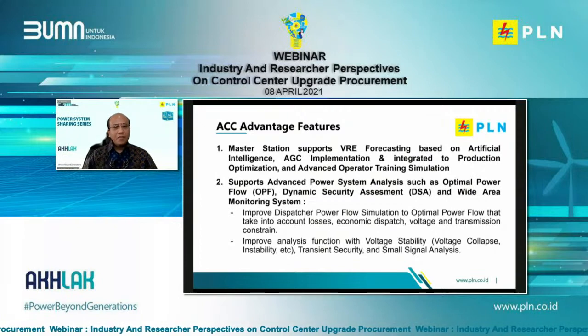Advanced power system analysis such as optimal power flow, dynamic security assessment, and wide area monitoring systems will improve the dispatcher's capability, moving from power flow simulation to optimal power flow, so we can take into account all the losses, economic dispatch, voltage, and transmission constraints, in order to achieve secure, reliable, quality, and economic operation of the power system.